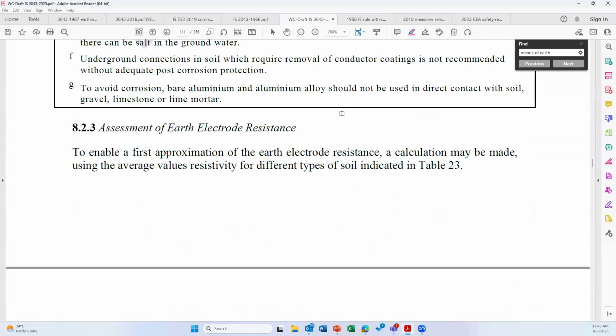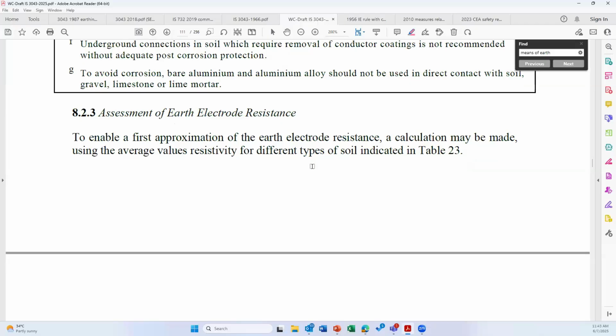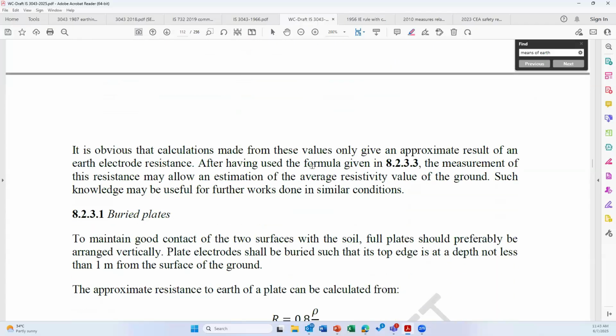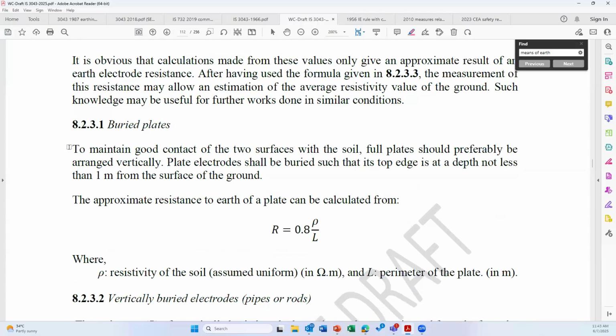New calculations of earth electrode resistance. Please note that calculating earth electrode resistance to 2 digits or 3 digits, a very accurate calculation, is absolutely not necessary. And maintaining a very accurate earth electrode resistance throughout the year was also not possible. As written in the foreword, the reliance on the earth for the fault return has been removed. The earth is nowadays used for fixing the voltage of the system. Earth electrode resistance is immaterial in this particular case. So simplified calculations are being included. These are from the IEC standard.